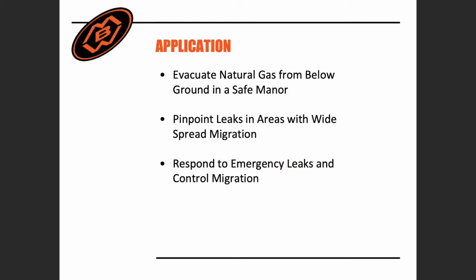We have added an LEL sensor that monitors LEL levels in real time while running the V.E.U. This is the only gas extractor on the market that can do this, pinpointing where your leak is in a widespread migration. You can run up to 18 probes at one time and control every probe and port with a shutoff valve. Once the V.E.U. is running for a little while, you will start to see the LEL levels decreasing in each bar hole. If one hole or multiple holes are staying consistent, then you have pinpointed the leak.